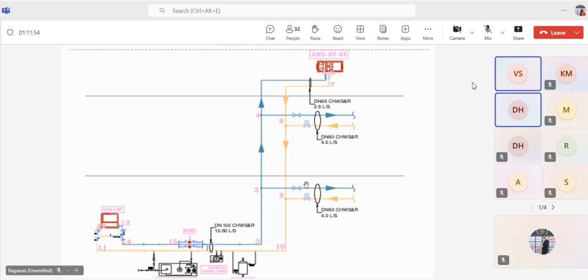Yes, basically we calculate the flow rate for a particular floor and add up all the flows, and then we find the total flow rate. Yeah, correct. And in the firefighting system, this is not the topic of firefighting, but in the firefighting system, every sprinkler has a different flow, so we have to calculate the flow rate of every sprinkler and add up to the main branch header. No, firefighting is a different topic. Usually in firefighting, you have coverage areas. Based on the coverage areas, for example, you have the hydraulic area, ordinary occupancy. Yes, the hydraulic area is the coverage area. Based on the hydraulic coverage area, how to calculate?